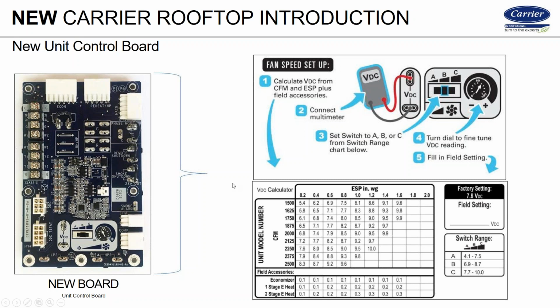Well, that's great. You'll run in heating and cooling. The motor's not going to overamp, as I mentioned yesterday, but you could have noise issues. If we're running higher air speeds than we need across the evaporator coil in cooling, we may not get the dehumidification that we need. And of course, with higher airflow in heating, our temperature rises are going to be lower, so you're going to have cooler discharge air. So setting C and 100% on the potentiometer really isn't the right way to do it.